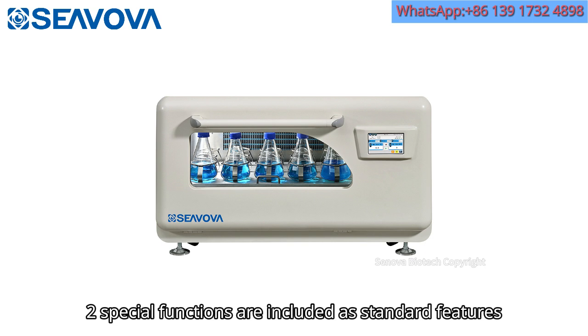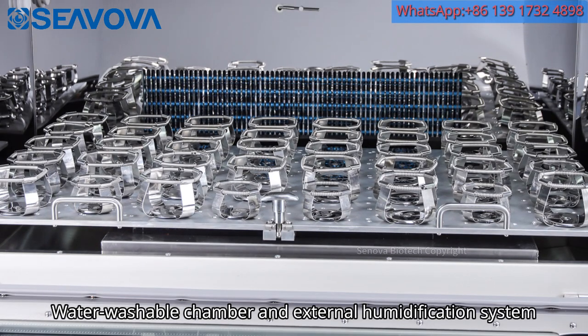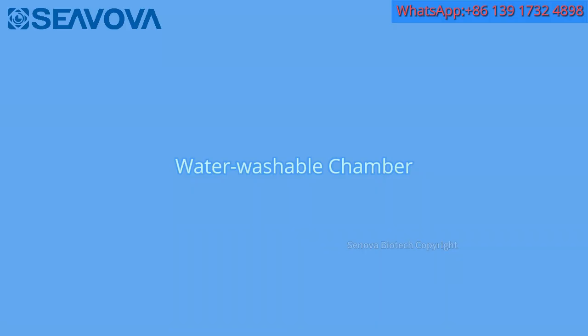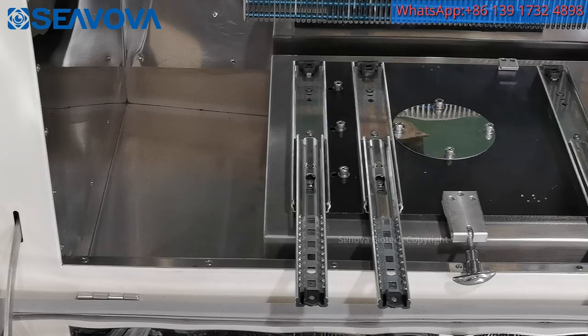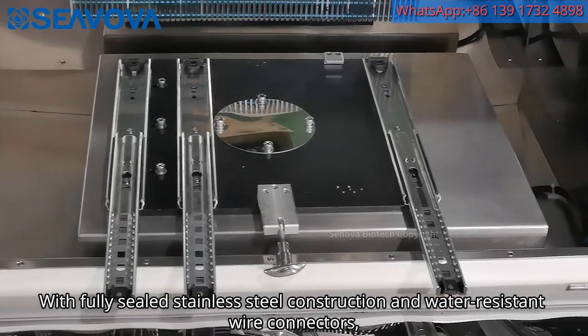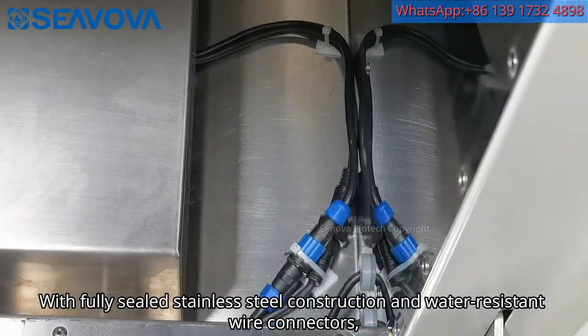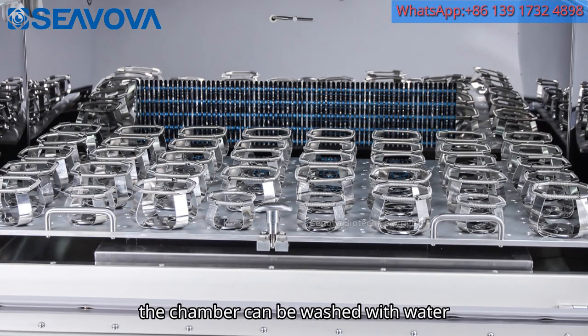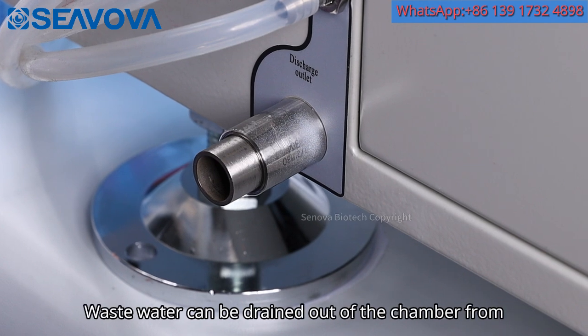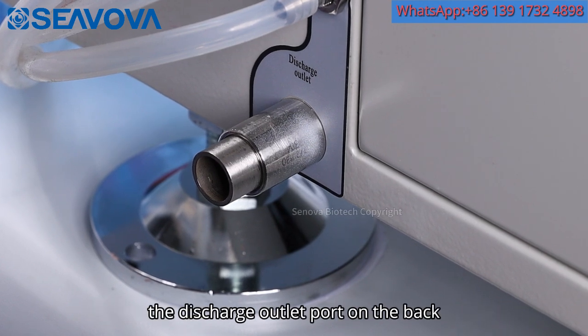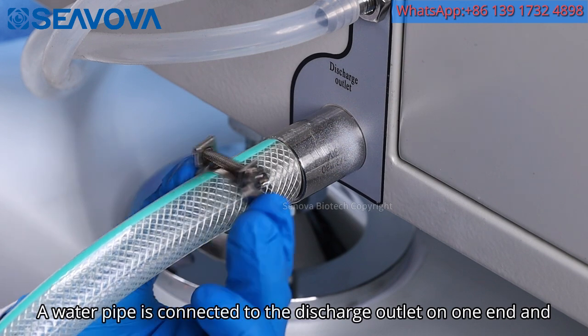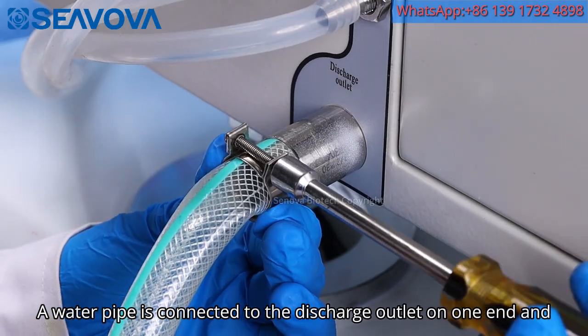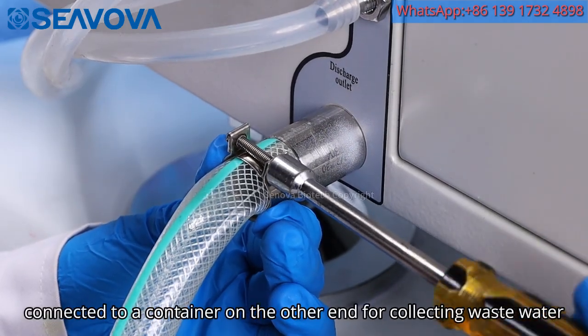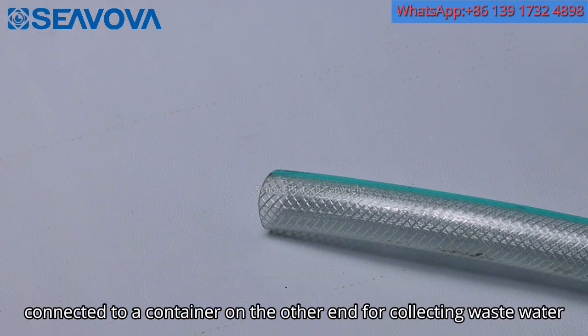2 special functions are included as standard features: water washable chamber and external humidification system. 1. Water washable chamber. With fully sealed stainless steel construction and water-resistant wire connectors, the chamber can be washed with water. Wastewater can be drained out of the chamber from the discharge outlet port on the back. A water pipe is connected to the discharge outlet on one end and connected to a container on the other end for collecting wastewater.